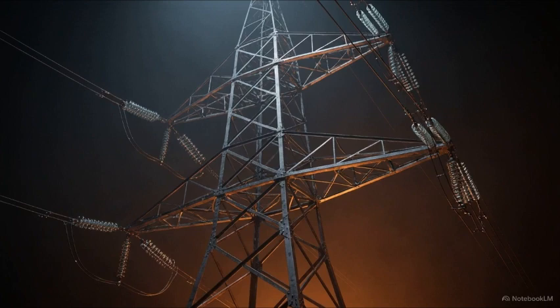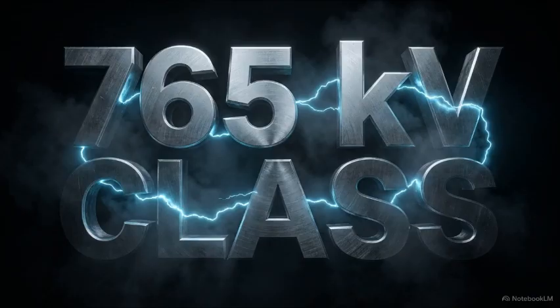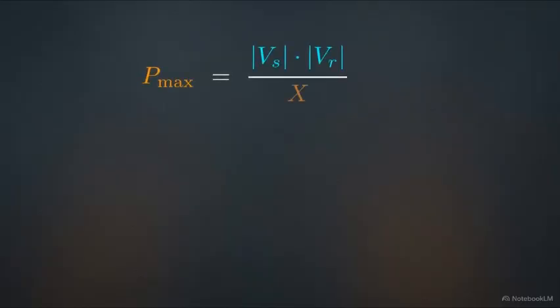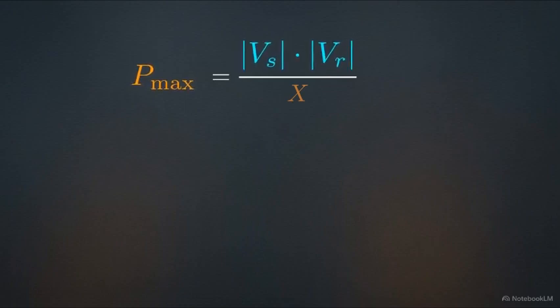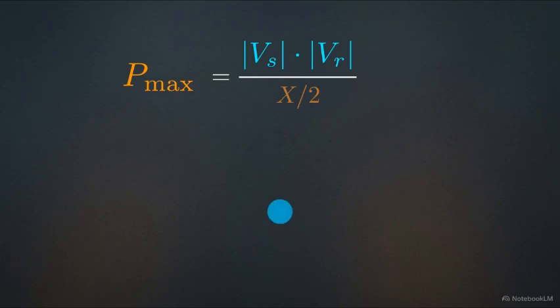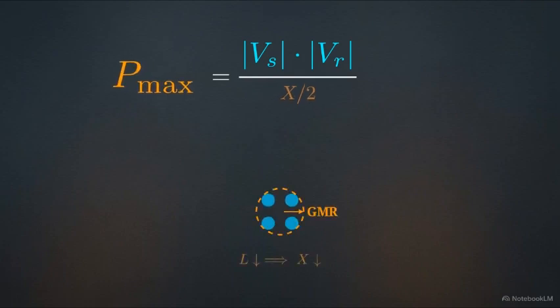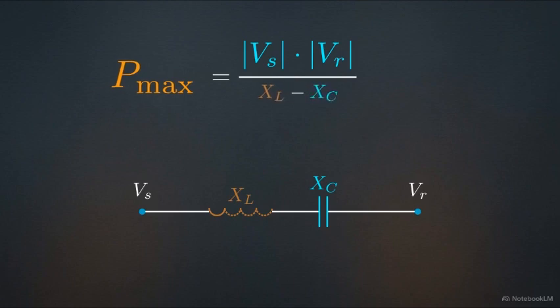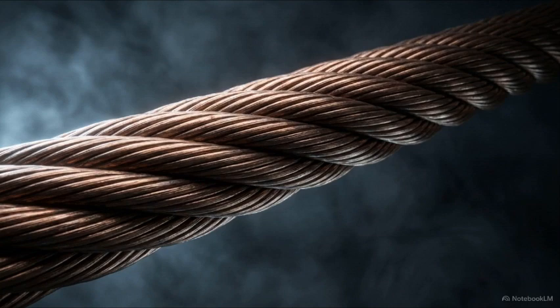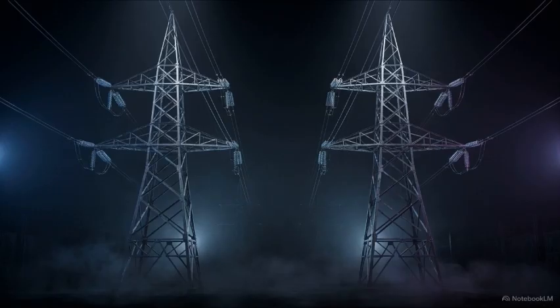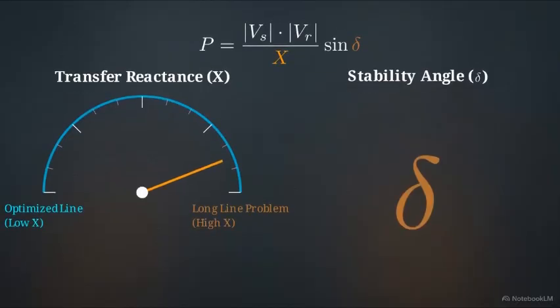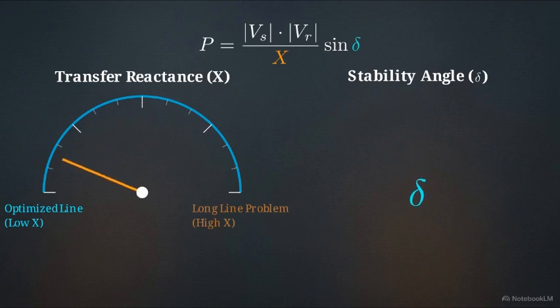Once the power leaves the plant, it travels down the wires, where the primary engineering strategy is scaling the system up to extra high voltage. In the maximum power transfer equation, upgrading voltage exponentially boosts stability. Engineers also shrink the denominator, X, inductive reactance. Erecting parallel lines cuts reactance in half. Bundling conductors reduces magnetic inductance. Finally, inline series capacitors mathematically subtract from positive reactance. Every structural change to wires, from bundling cables to adding entire parallel towers, serves the singular mathematical purpose of shrinking electrical impedance to keep the stability angle low.